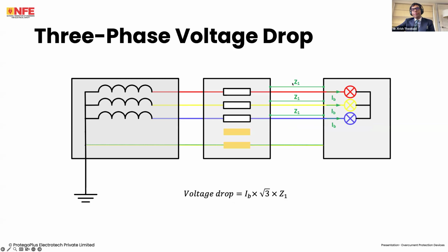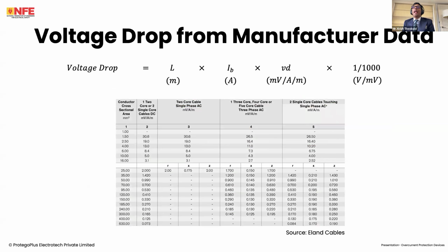Three-phase voltage drop is a combination of all three lines. So it is the design current multiplied by root 3 for the three-phase circuit, and the impedance of the conductors, because this is conventionally taken to be the same. So that's that. Now, how do we calculate voltage drop?